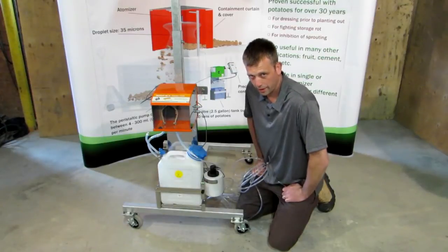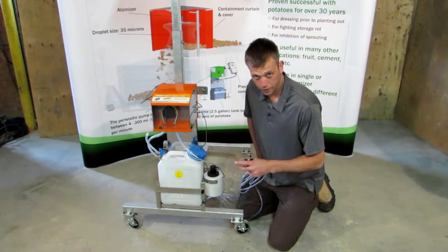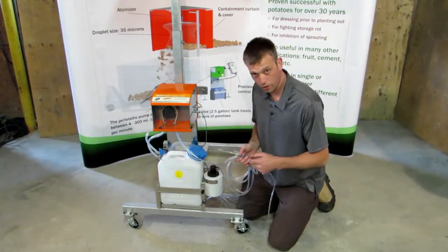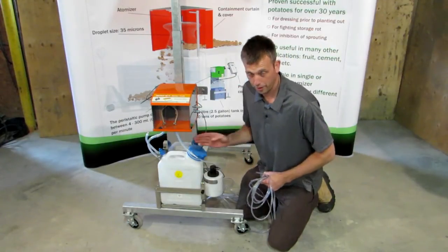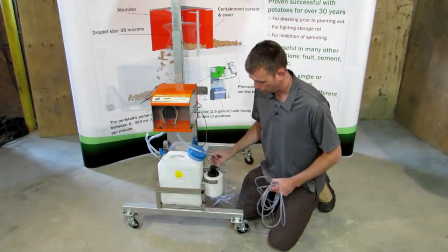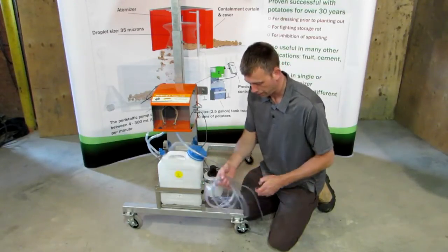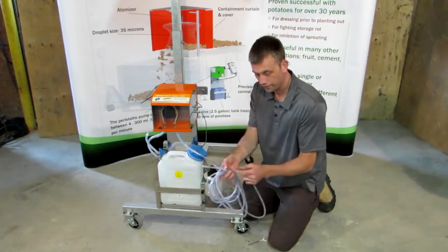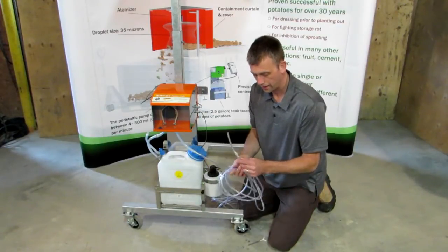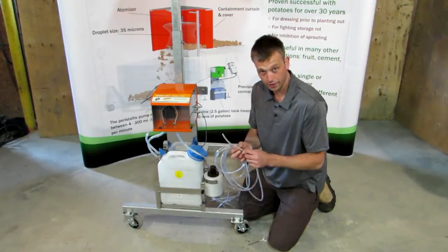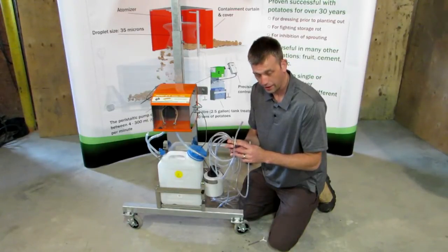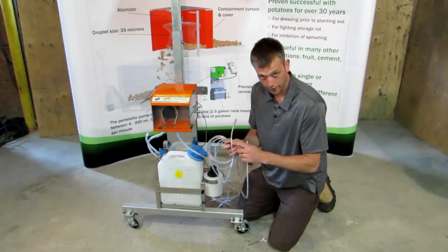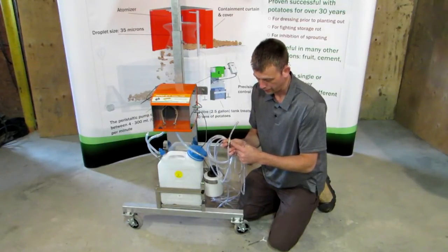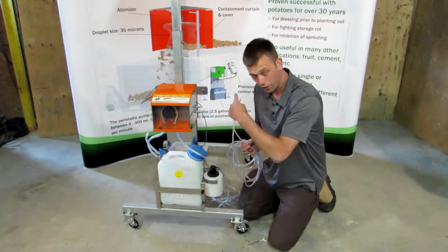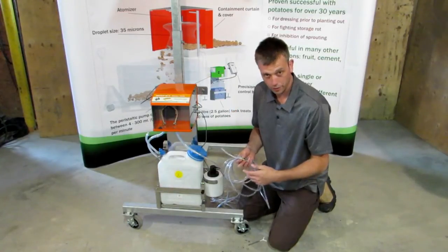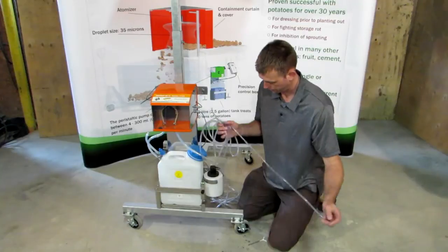Okay, once we've got the atomizer installed, we're going to run the hoses to the atomizer. Now there's going to be 2 hoses going up, one from the pump box itself, and then one from our flush tank here. So we supplied a hose for the flush tank that has a one-way valve installed in it already. Please pay attention to the arrow on that beige valve. We want that arrow to be going towards the atomizer, otherwise no flush water will be able to reach the atomizer.